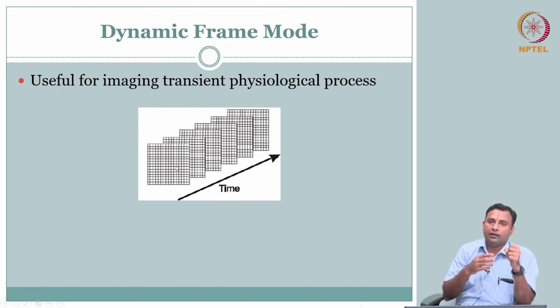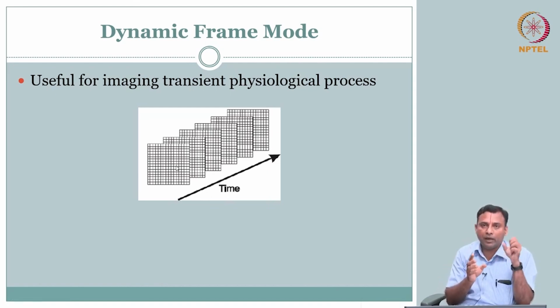Then I can get ECG, right? So I know with high precision which part of the ECG, which part of the heart cycle I am imaging. So I can trigger everything, starting my scintigraphy detector at the start of, say, the R wave. So I can time that. From there on I can acquire this delta t over the full cycle. So this is one way of dynamic frame.